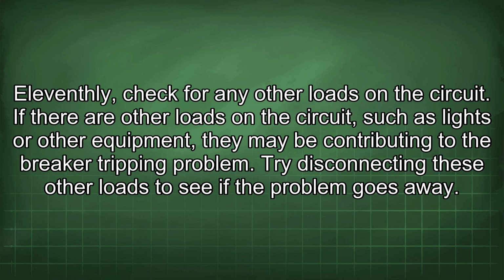11thly, check for any other loads in the circuit. If there are other loads on the circuit, such as lights or other equipment, they may be contributing to the breaker tripping problem. Try disconnecting these other loads to see if the problem goes away.